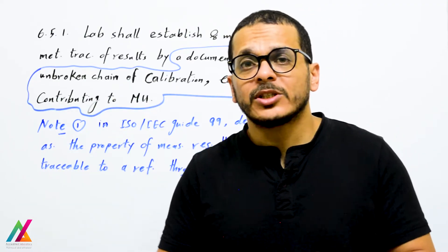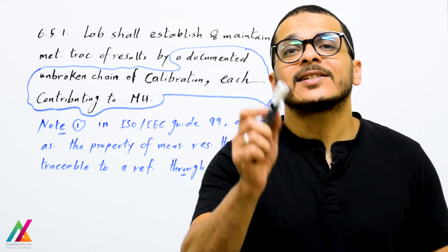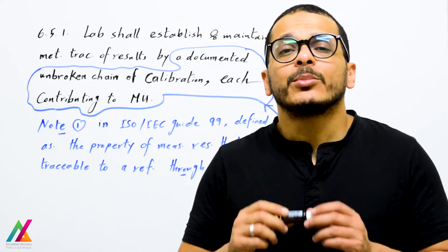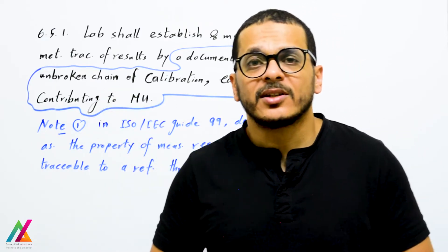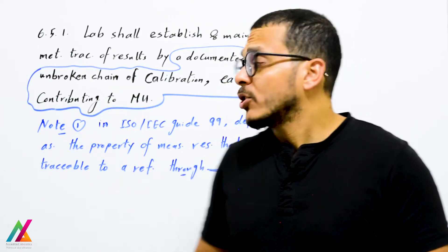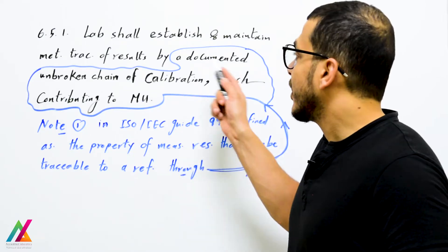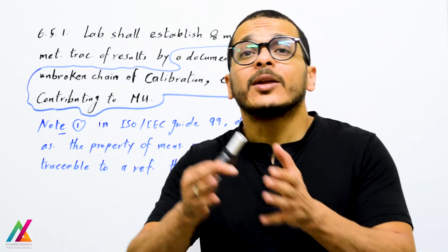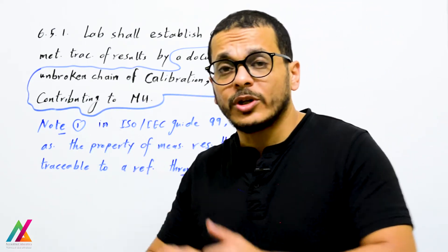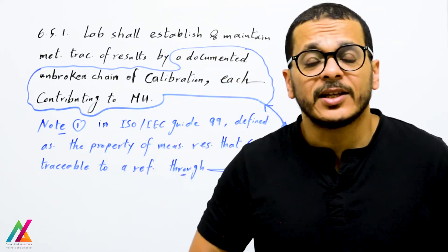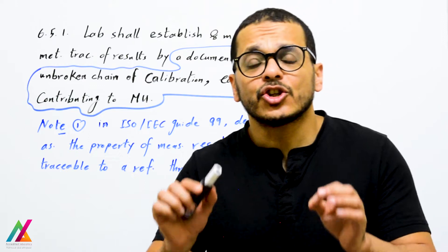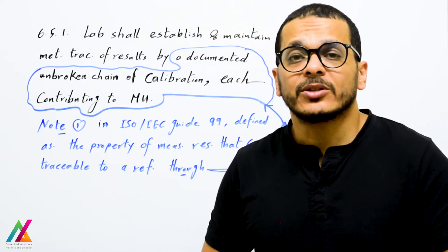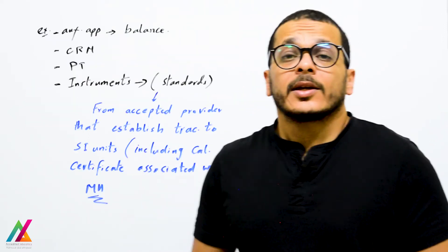For each piece of equipment you will find a certificate including measurement uncertainty. It will be a documented unbroken chain of calibration for all equipment inside the lab, each contributing to measurement uncertainty.